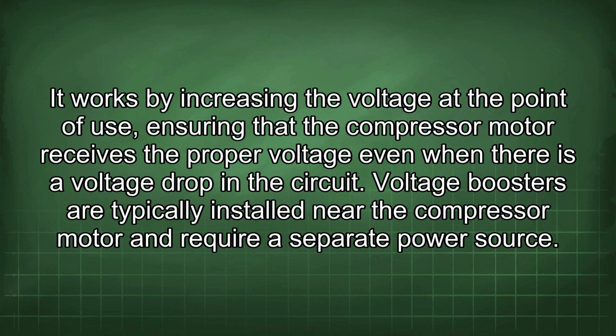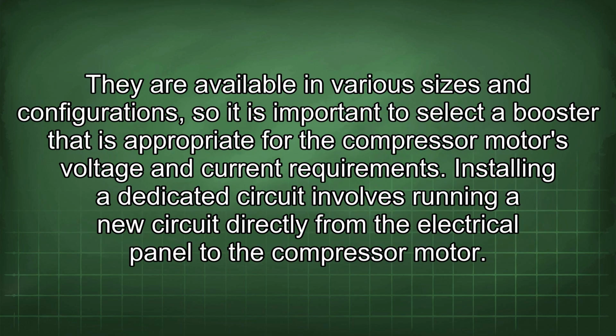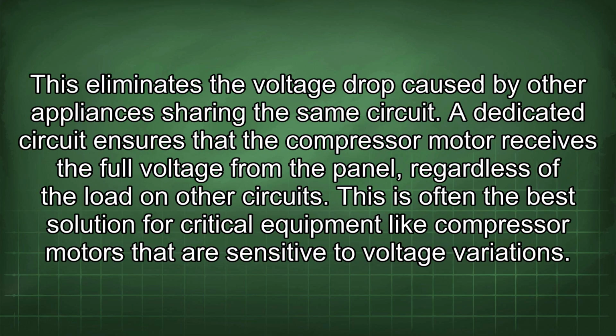Voltage boosters are typically installed near the compressor motor and require a separate power source. They are available in various sizes and configurations, so it is important to select a booster that is appropriate for the compressor motor's voltage and current requirements. Installing a dedicated circuit involves running a new circuit directly from the electrical panel to the compressor motor. This eliminates the voltage drop caused by other appliances sharing the same circuit. A dedicated circuit ensures that the compressor motor receives the full voltage from the panel, regardless of the load on other circuits. This is often the best solution for critical equipment like compressor motors that are sensitive to voltage variations.